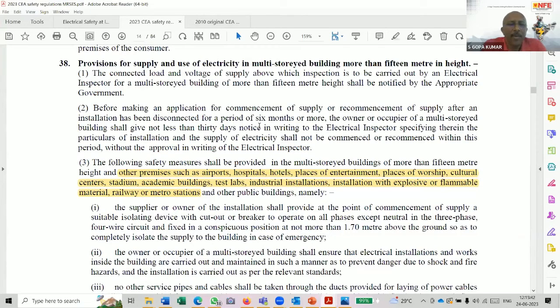So, sir, according to you, all high-rise buildings, multi-storied buildings, more than 15 meters need inspection, except these airport, hospital, hotels, and other such places. See, so these don't need, as per regulation 38.3, the following protections or clauses should be applied for the buildings having height more than 15 meter plus the other buildings. As per regulation 38, the building having height more than 15 meter should get permission from electric inspector. Is it right?